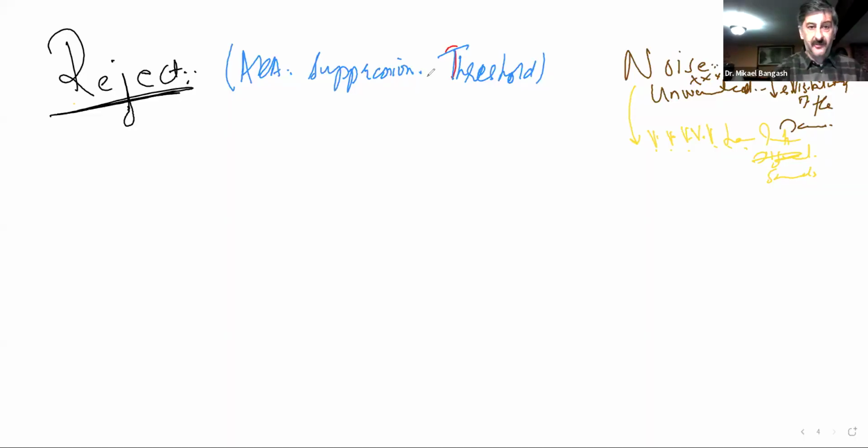So what is that rejection going to do? It is mainly a mechanism that is going to eliminate weak intensity signals off your image. What do we call those weak intensity signals? They were the ones which were noise. Did that make sense? So reject pretty much was or is a suppression or threshold.